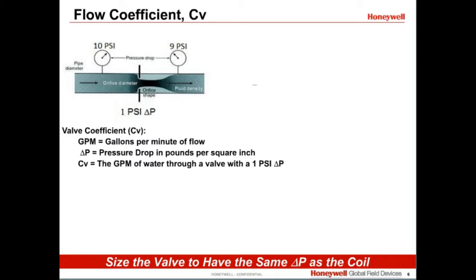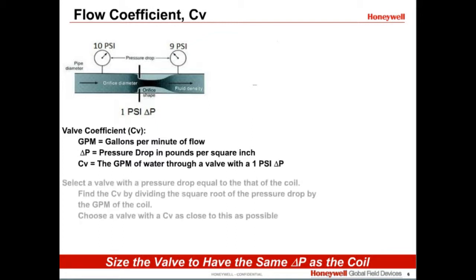good temperature control. If the CV is too large, the valve will operate most of the time at a very small opening and can result in cavitation that could damage the valve and very poor temperature control. If the valve CV is too small, it may not provide enough flow for the application, resulting in insufficient heating or cooling. To properly size the valve, it should have about the same pressure drop as the coil it controls.